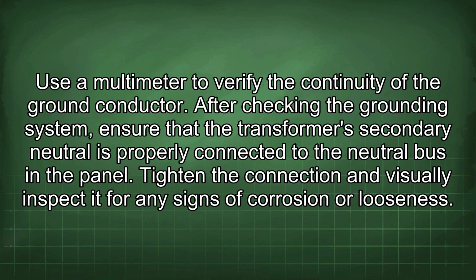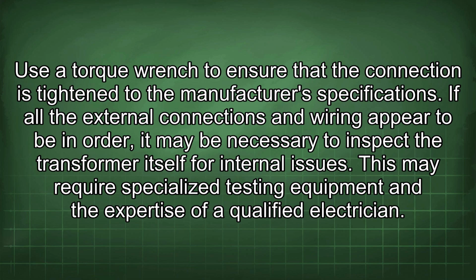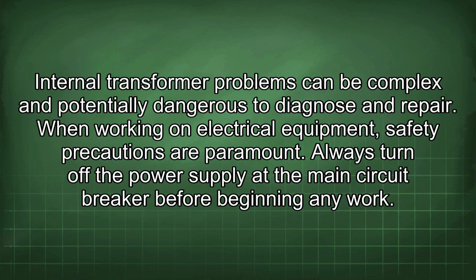After checking the grounding system, ensure that the transformer's secondary neutral is properly connected to the neutral bus in the panel. Tighten the connection and visually inspect it for any signs of corrosion or looseness. Use a torque wrench to ensure that the connection is tightened to the manufacturer's specifications. If all the external connections and wiring appear to be in order, it may be necessary to inspect the transformer itself for internal issues. This may require specialized testing equipment and the expertise of a qualified electrician. Internal transformer problems can be complex and potentially dangerous to diagnose and repair. When working on electrical equipment, safety precautions are paramount.